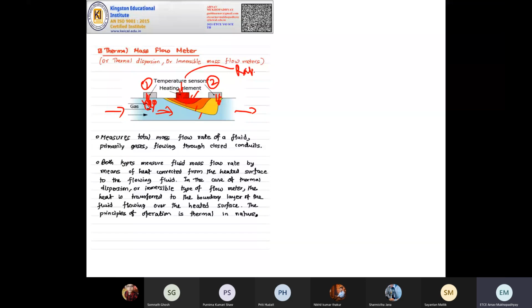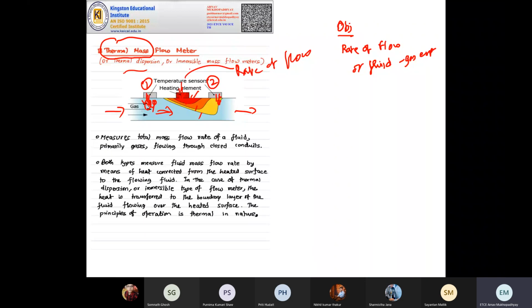Remember, the objective here is the rate of flow of fluid, especially gas. This is the thermal mass flow meter, thermal mass or heated mass flow meter. It has other names: thermal dispersion flow meter, immersible mass flow meter. It always measures the total mass flow rate of fluid, mainly used for gases, and it uses a closed conduit. A closed conduit means an enclosure, like a pipeline. You cannot measure the thermal mass flow in an open area. So you understand the concept.